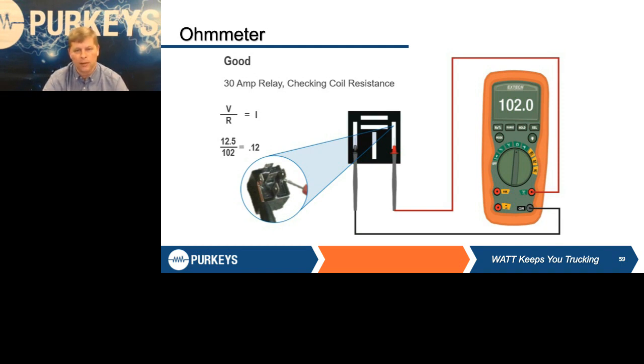And that's where it goes back to, you can check things, checking that blower motor. If you did the math and says, ooh, based on this, that blower motor is going to pull 150 amps, that's probably not the right resistance. Or go the other direction, says the blower motor is only going to pull 2 amps, that's probably not the right resistance either. So it does at least give you a way to check it. Does that seem correct?